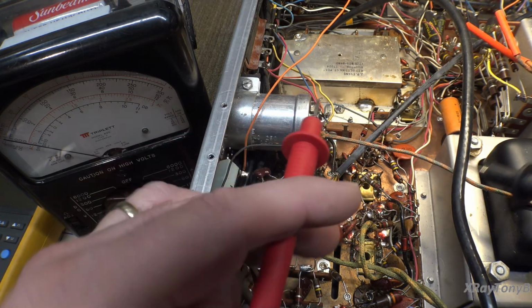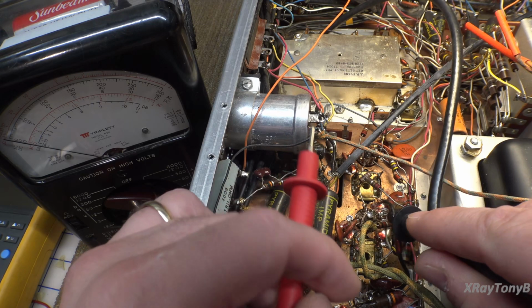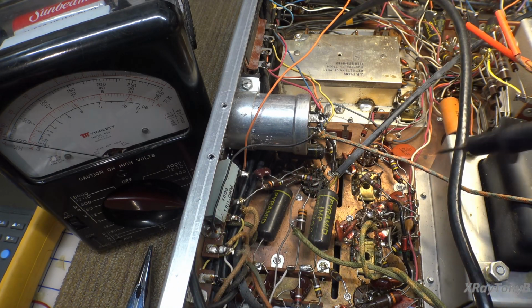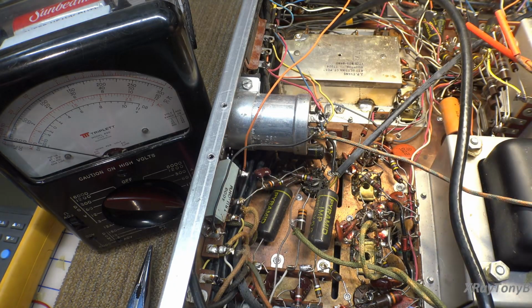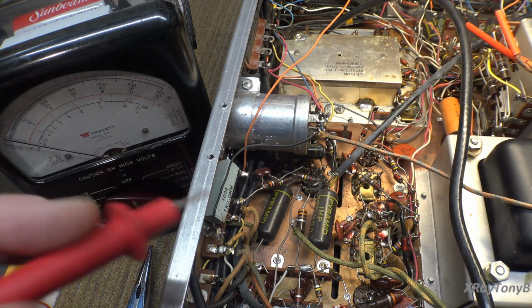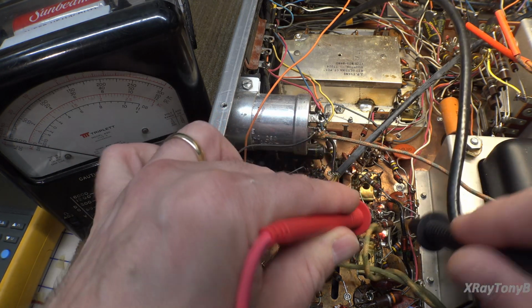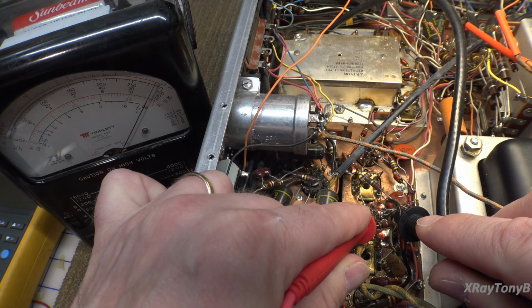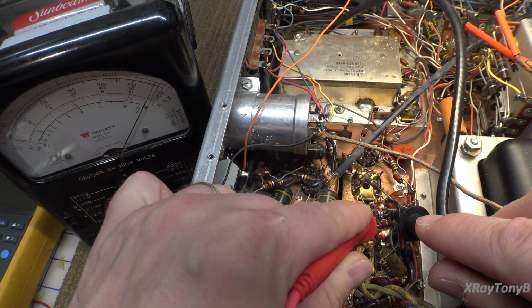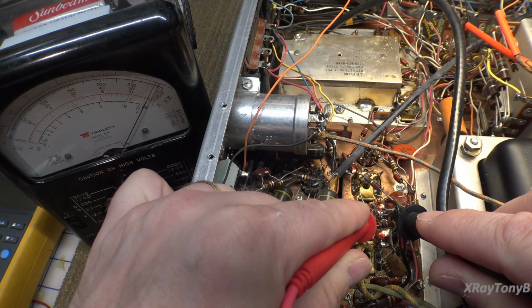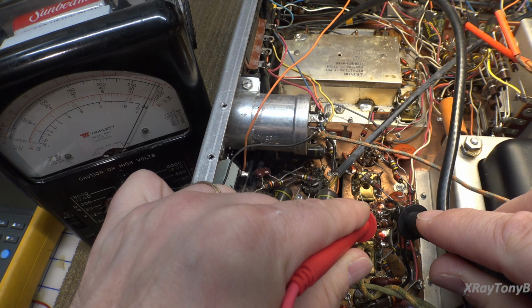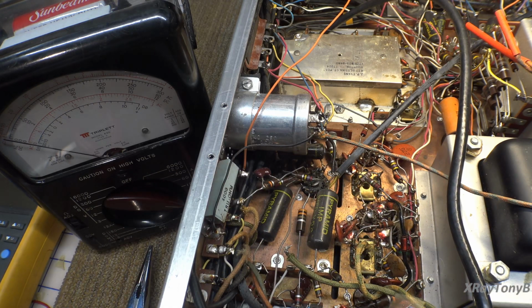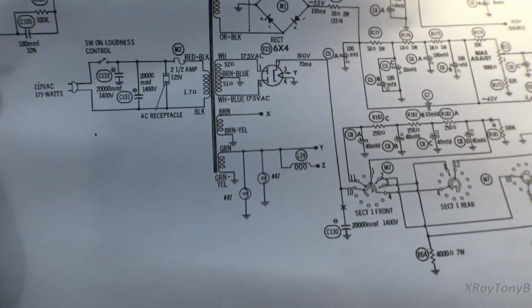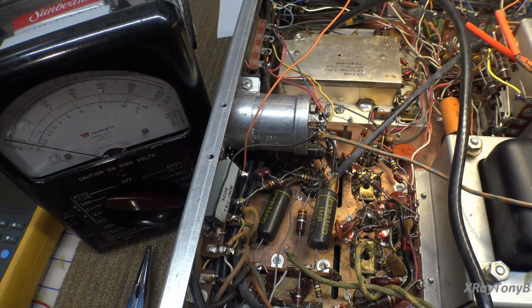And you can see there's no short. If I go to this gray wire, you see I removed this gray wire down here. It snakes its way all the way around, clear to the other side of the chassis. And if I measure from ground to that, there's your short. Now I'm on times 10 right now, meaning whatever I read, you times it by 10. So I'm getting about 3 or 4 ohms, which could very well be those two indicator bulbs. We'll have to find those. We could be reading that, but it is not a dead short.